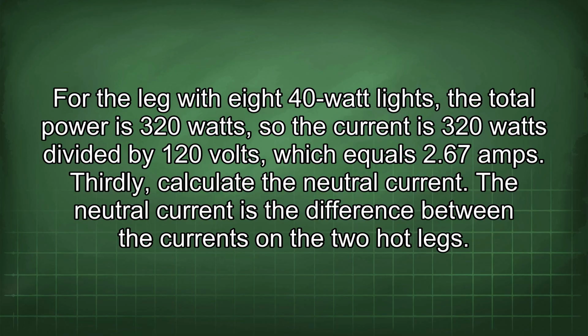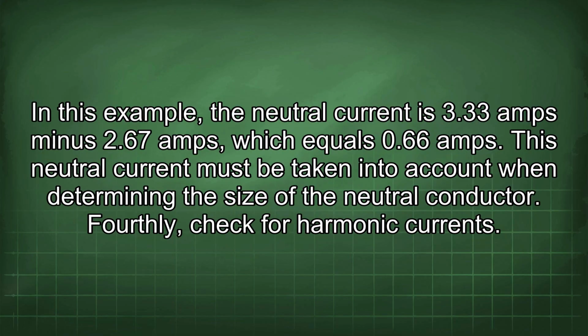Thirdly, calculate the neutral current. The neutral current is the difference between the currents on the two hot legs. In this example, the neutral current is 3.33 amps minus 2.67 amps, which equals 0.66 amps. This neutral current must be taken into account when determining the size of the neutral conductor.